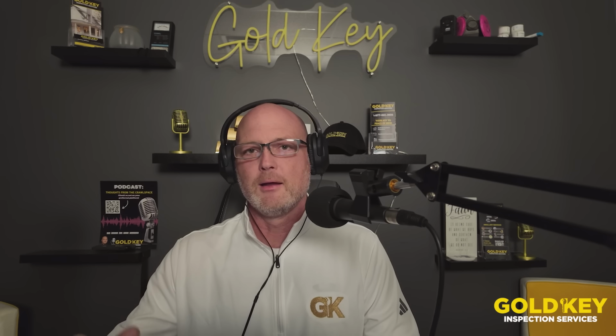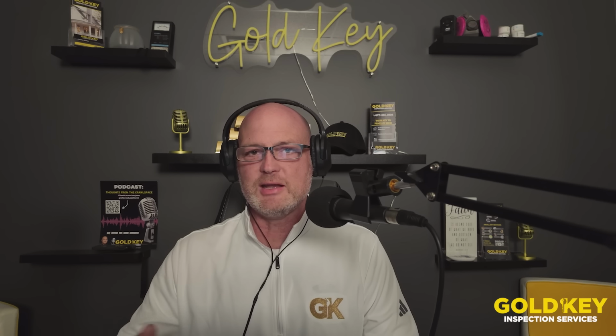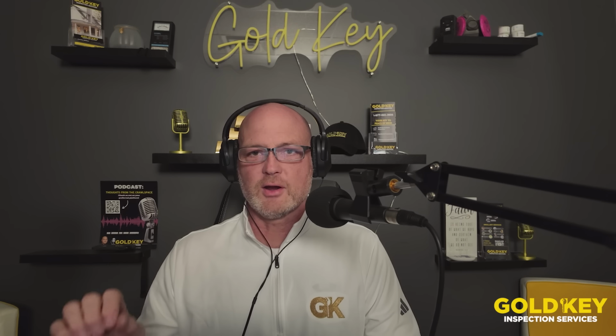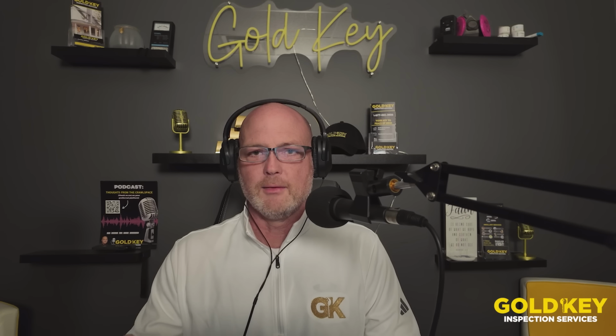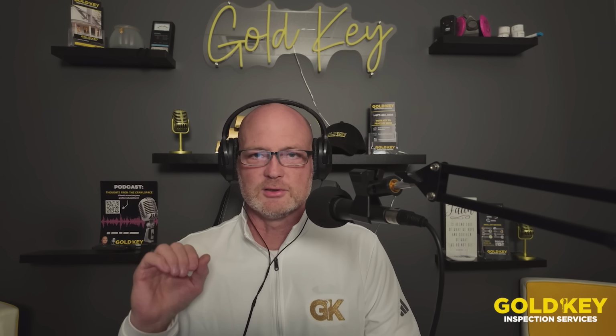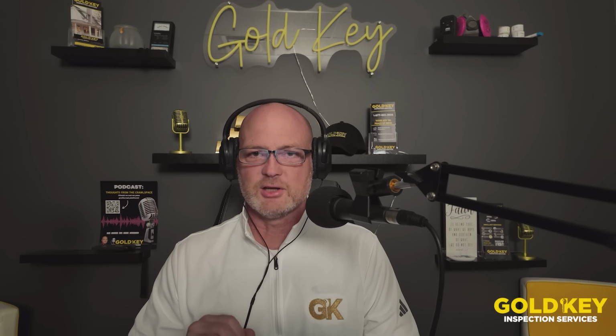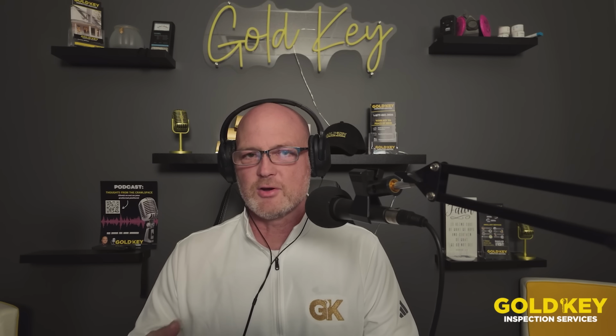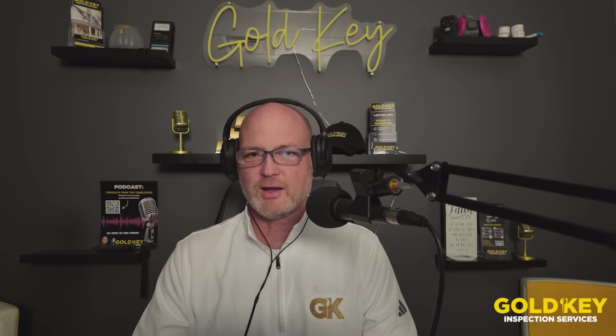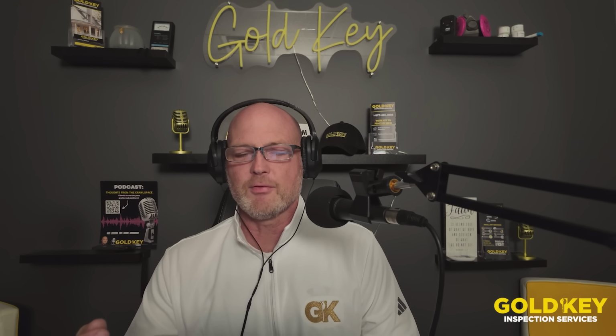Shut down. But it won't give it enough time to dehumidify the air. And so you're going to get a lot of cold, and then it's going to shut off. And it's going to shut off, turn on again, and then it's going to shut off. And none of those times are you getting really good dehumidification. And so a couple of things happen there.